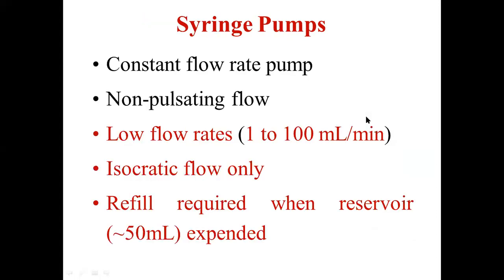Next, syringe pumps. These syringe pumps are also widely used pumps in HPLC. Whenever a constant flow rate is required, they are just like a syringe. You have all seen a syringe. A syringe is capable of holding several milliliters of solvent, so the volume of the solvent will be definite and fixed. Whenever a definite volume of the mobile phase is moved at a fixed flow rate, and this condition is required to be fulfilled, then we will use syringe pumps, because they will always produce a constant flow rate.